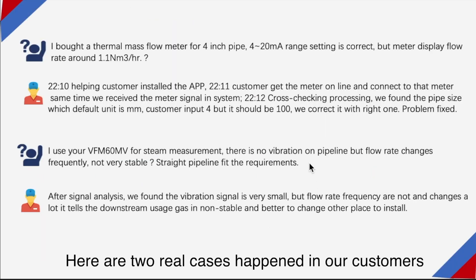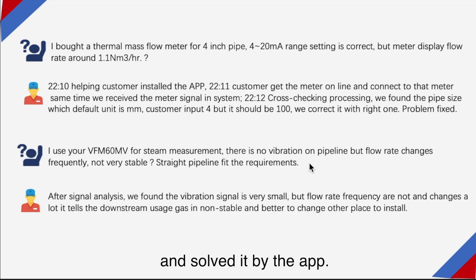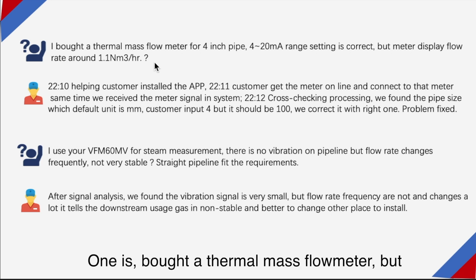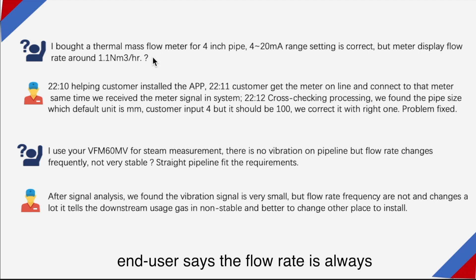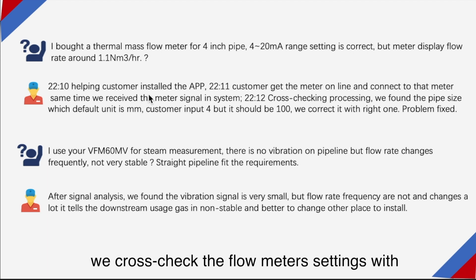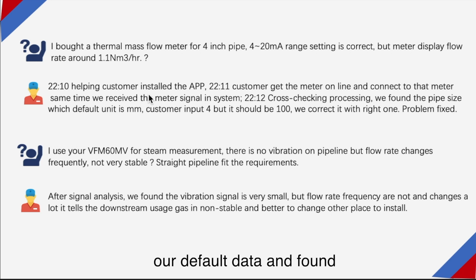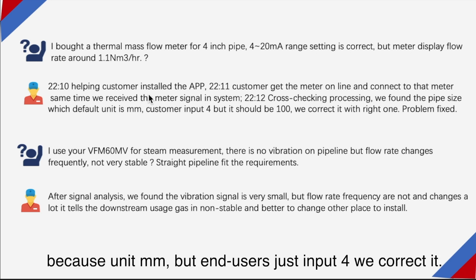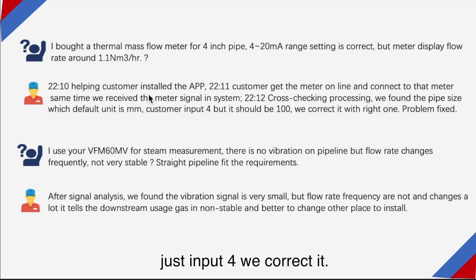To help users find the real cause of problems and solve them in a time-saving and efficient way, here are two real cases from our customers solved using the app. One is about a mass flow meter where the end user reported the flow rate was always in a very small range. After getting the meter online, we cross-checked the flow meter settings with our default data and found the pipe size should be 100 because the unit is millimeters, but the end user had input 4.